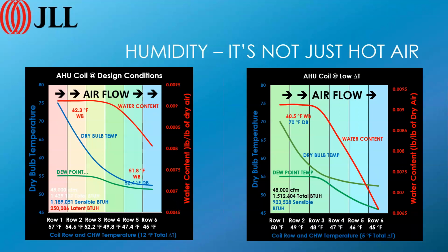That's normal. Around 1.4 million BTUs sensible for 48,000 CFM. When you move over to the right-hand coil, same airflow, 48,000 CFM. And now we've got a delta T issue on the coil. It's now a 5-degree delta T. 45-degree water going into the coil, 50-degree coming out.